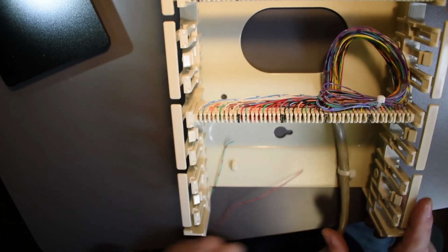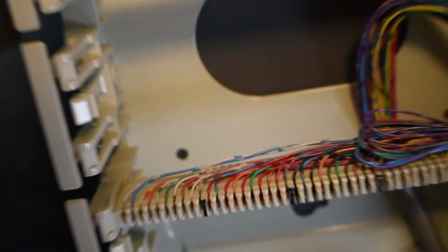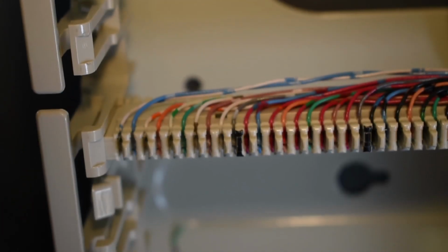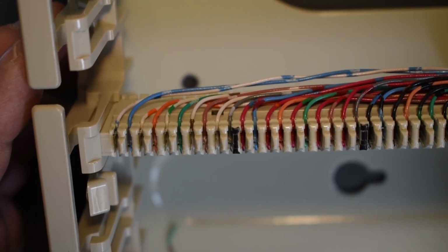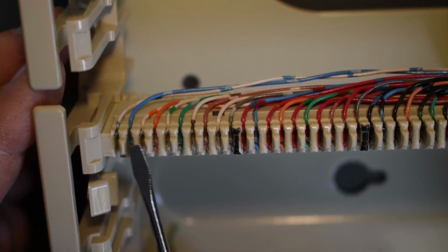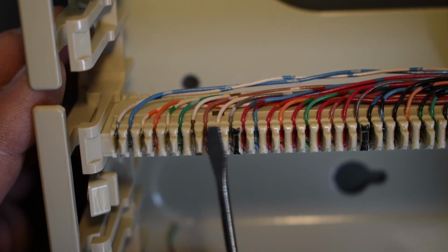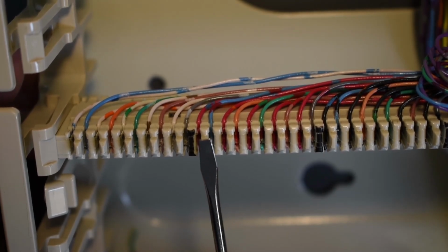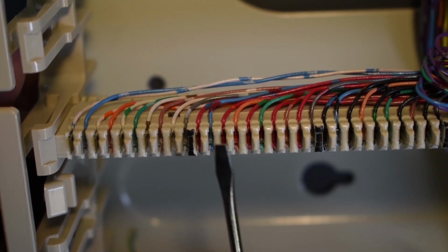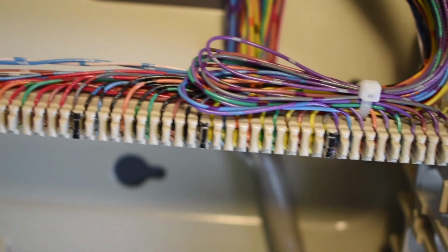Now, let's see what we have here. Just got to make sure all the wires are nicely punched and nothing has jumped on us. All right. So here's blue pair, orange pair, green pair, brown pair, and slate pair. All the white group wires. White goes first because it's the group. Here's the red group. All right. Blue, orange, green, brown, slate, and red always first. Here's the black, and here's the yellow, and here's the violet.